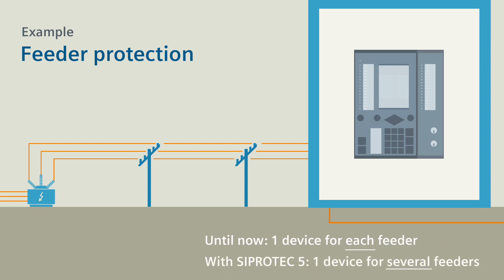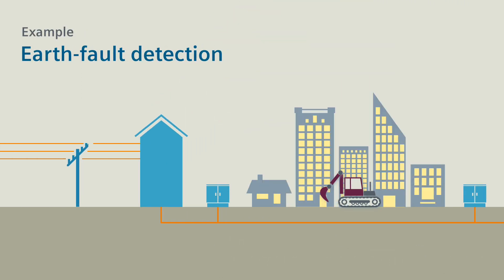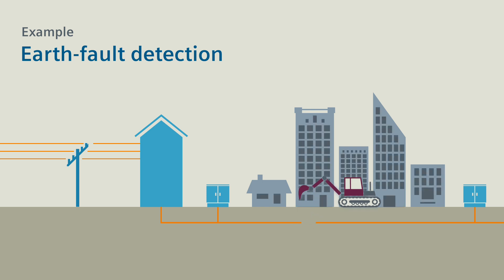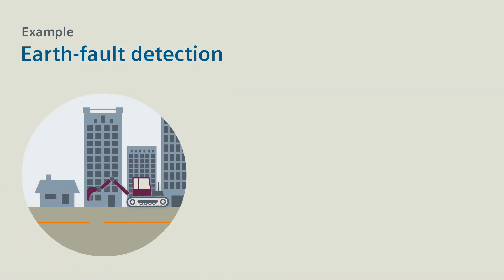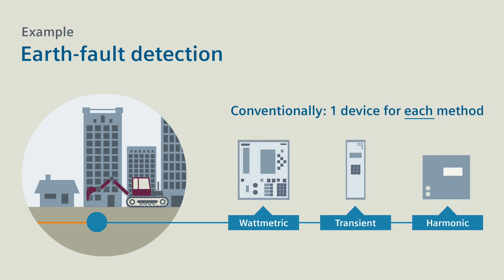one single device is sufficient to simultaneously protect several feeders. Example: Earth Fault Detection. 80% of all faults are earth faults, caused by construction among other things. Solved conventionally, you utilize an independent device for each of the three detection methods: wattmetric, transient, or harmonic.